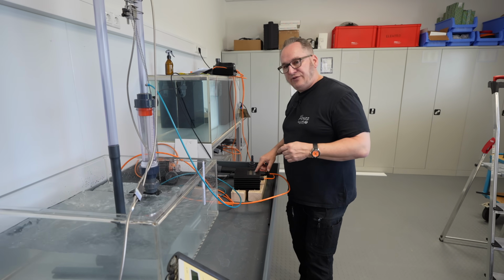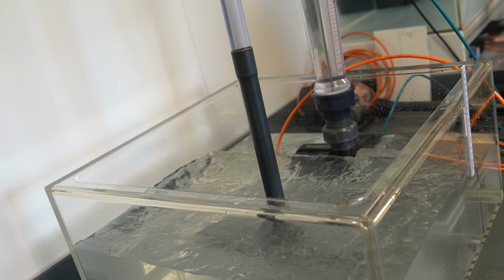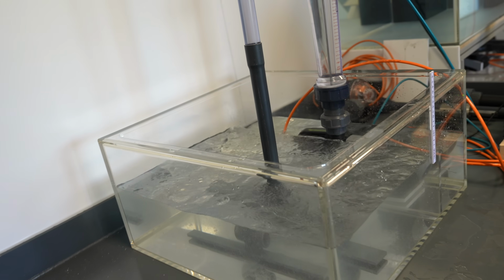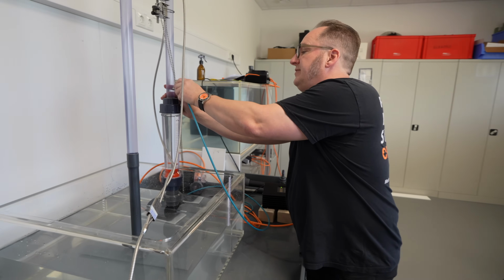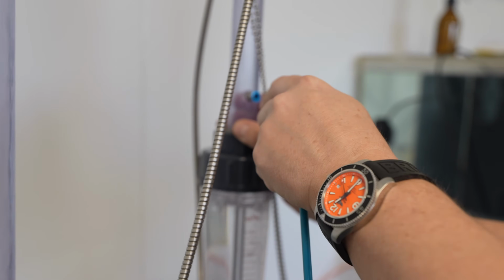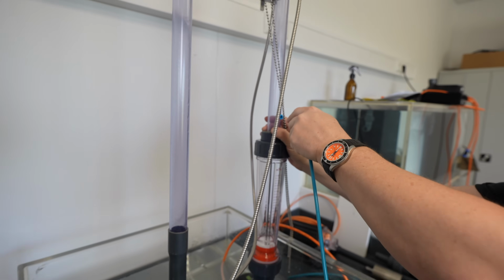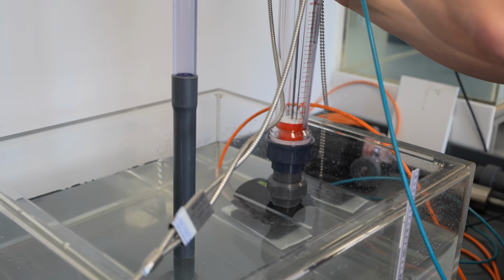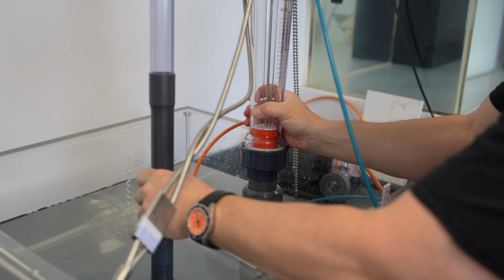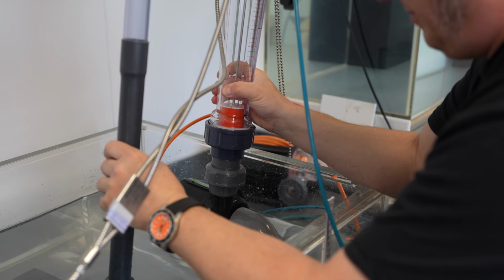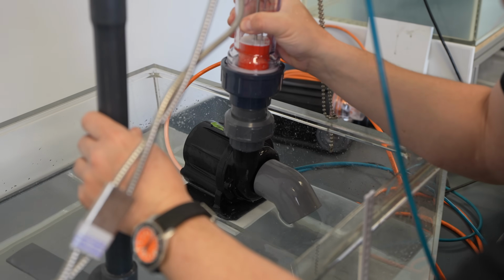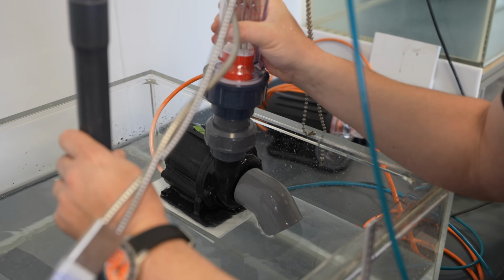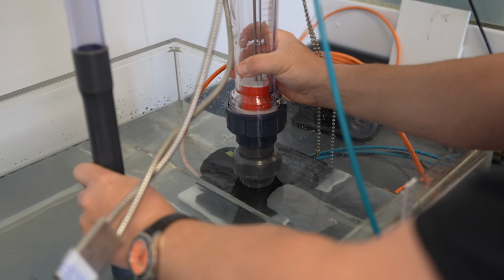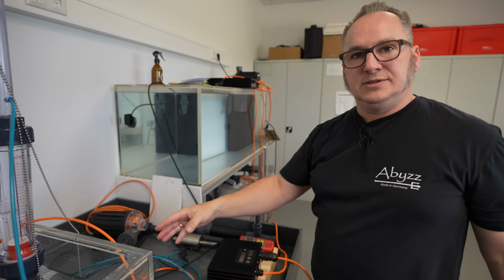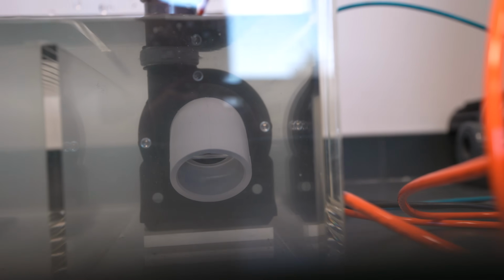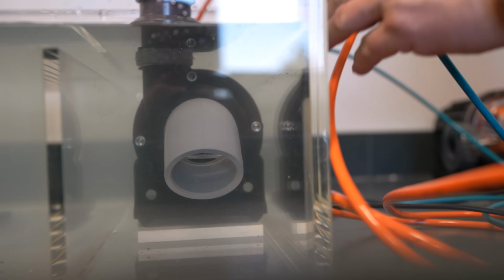I also wanted to show you the effect of the pump not wanting to start because it's got an air trap in, because that's something that we get very often. We'll now drain the system. And then we'll make sure that the pump has an air trap inside. So now the pump is empty. And now we have the situation that maybe the returning water has collected some air bubbles, an air trap into the pump, and you can actually see that there's a bubble right in front of that 45 degree.